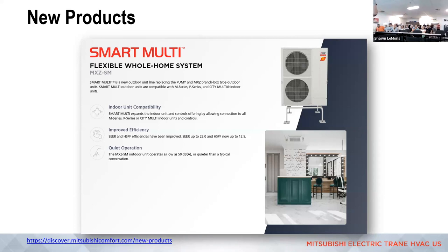So if you've got an existing home with a pretty high heat load and you need to put a cased coil in to take care of part of the house, or you want to put a ceiling cassette in the primary suite - it's not master anymore, it's primary - to take care of the envelope of the house where the insulation isn't that great, maybe they need a dedicated piece in the primary room or the room over the garage. You can do that with this smart multi application with less fear of oversizing or overshooting.